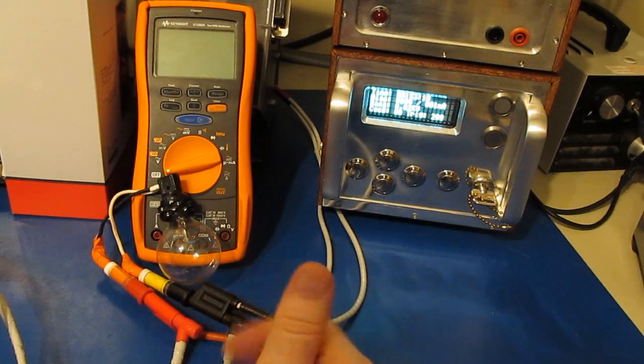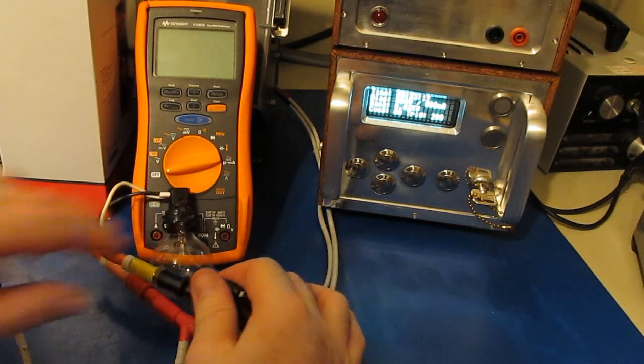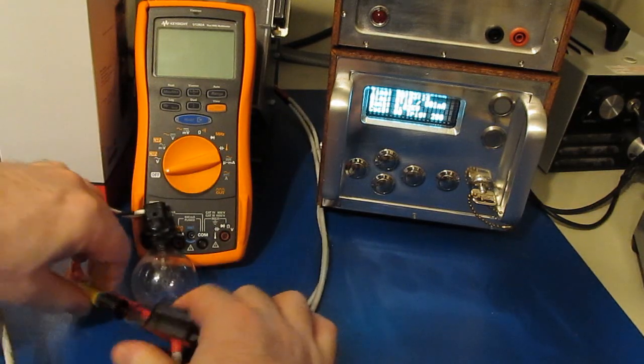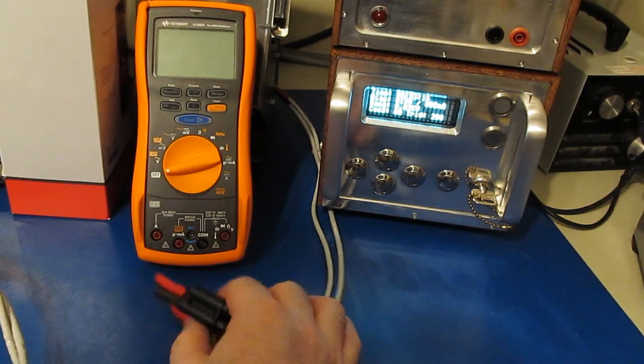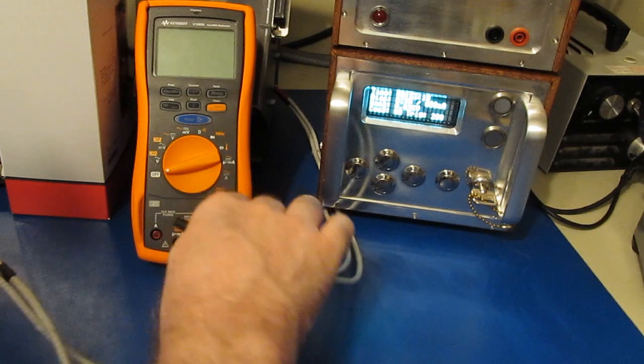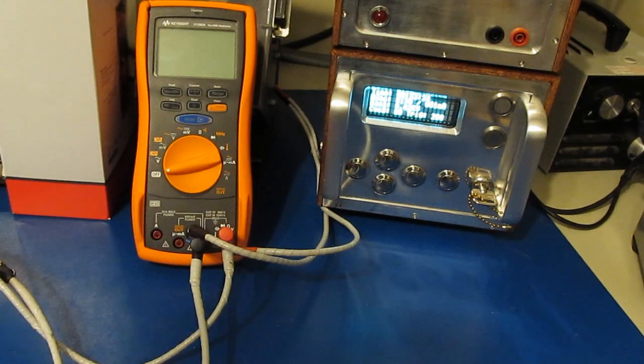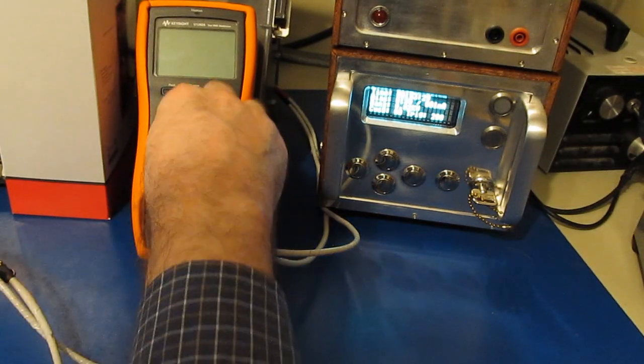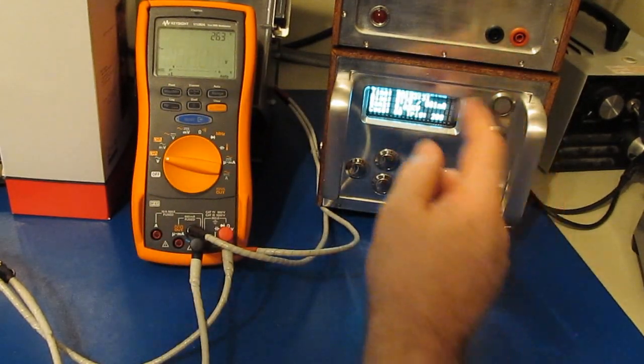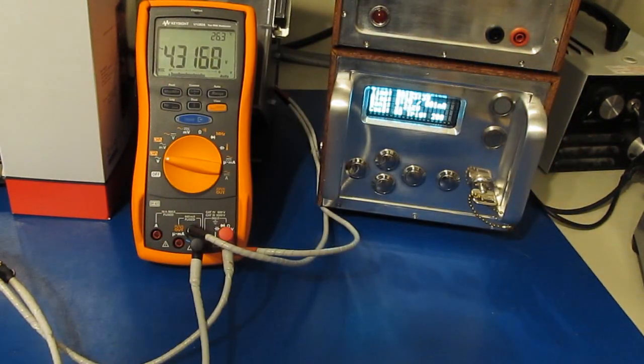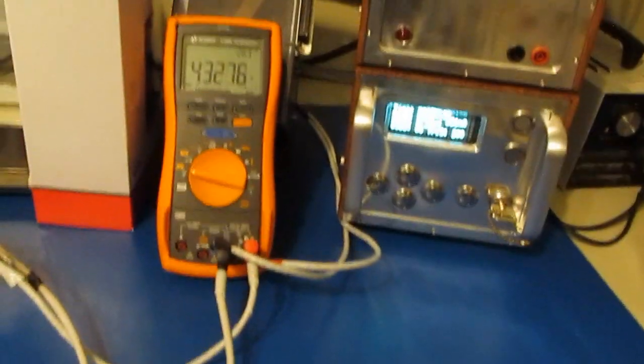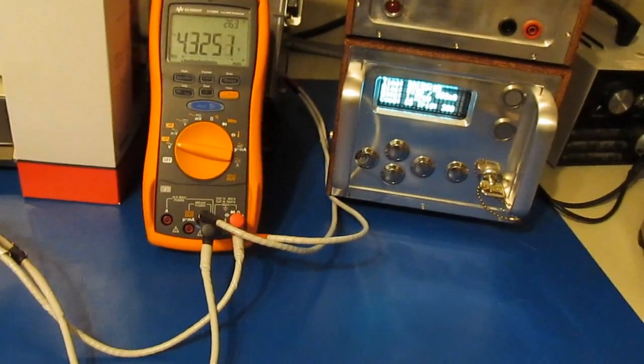You can see quite a bit brighter now. Things are starting to get a little serious. So again, this will be 4,000 volts peak, 100 microsecond full width half height, 2 ohm source impedance, positive and negative transients, 5 each with the meter set to each mode. Again, you can see the decay is a little quicker. Of course, we're activating those gas discharge tubes now.